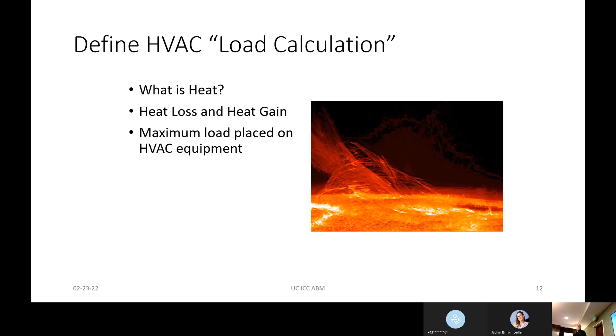That gives us the maximum load that will be placed on the piece of equipment. Now we're faced with a challenge in a home because we want to design it so it runs almost all the time at the very coldest conditions, but 99% of the time we're at a different condition, so it's oversized the rest of the time.